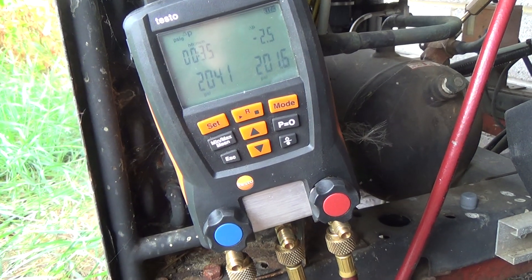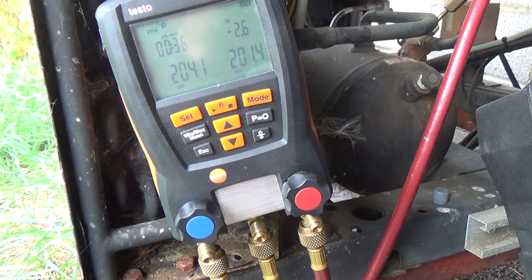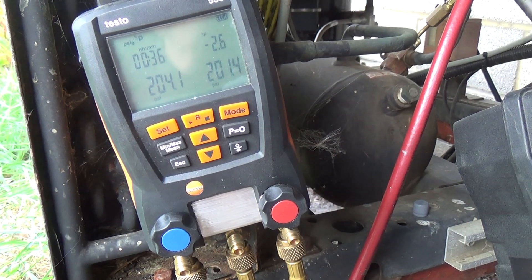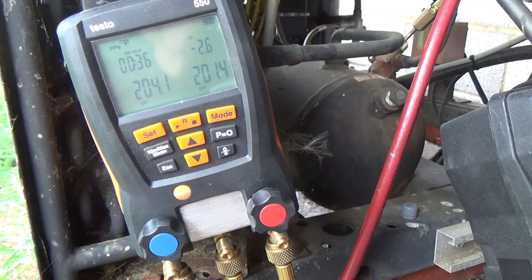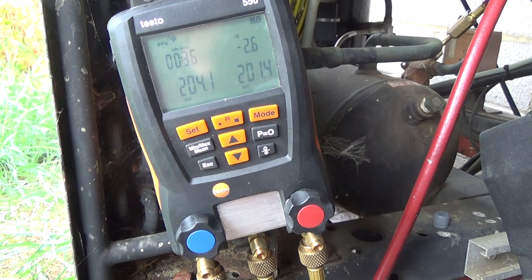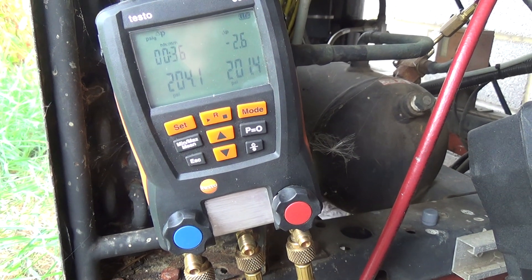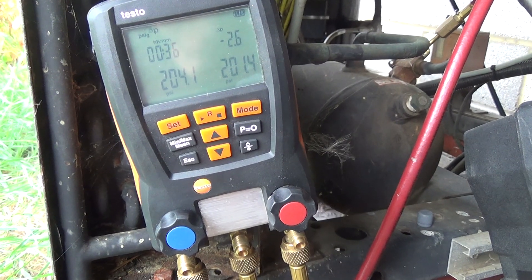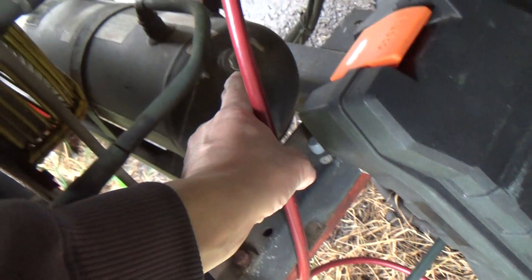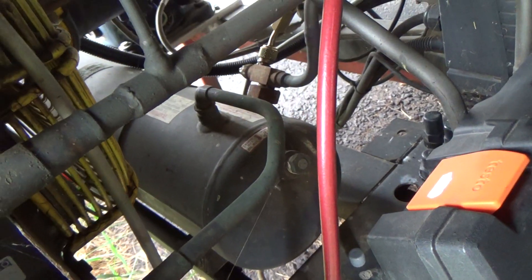Previously we'd lost about 30 PSI in about 5-10 minutes. And the heat recovery still had pressure - they're pressurised from the factory - and that new circuit still had pressure in it. I might get some leak spray and go round that plug while we're at it.